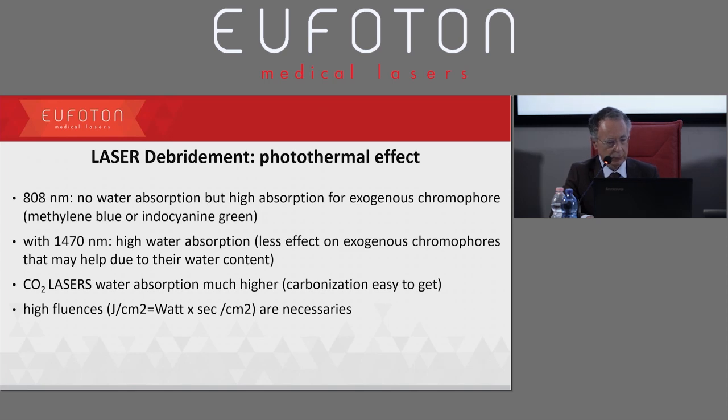1470 as well. 1470 has a high water absorption, and less chromophore absorption, but since chromophore is liquid, the water absorption allows us to use also the 1470, even though the wavelength of 808 is preferable.